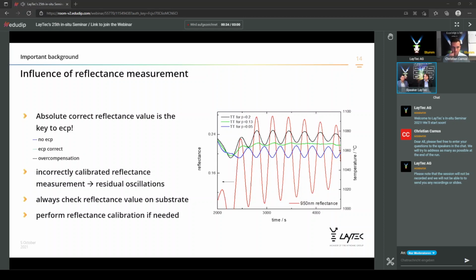If we would not do that, you can also display the raw voltage. That means no ECP. You will find an oscillating temperature measurement. This is the blue line below the green line. Or if you would have a wrong value for the reflectance, you might have oscillations on top of the real value. That is the black line, where we have, in this example, an overcompensation. So this is showing an incorrectly calibrated reflectance will cause residual oscillations.